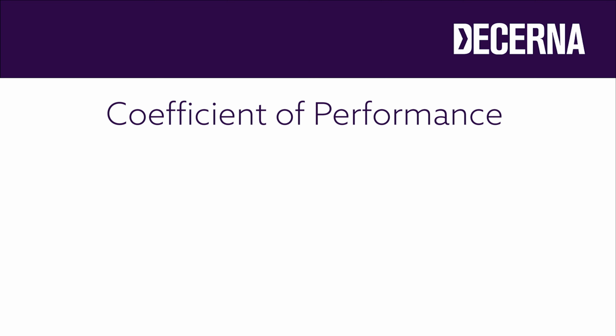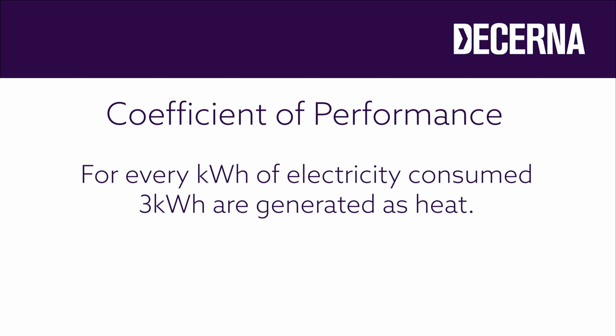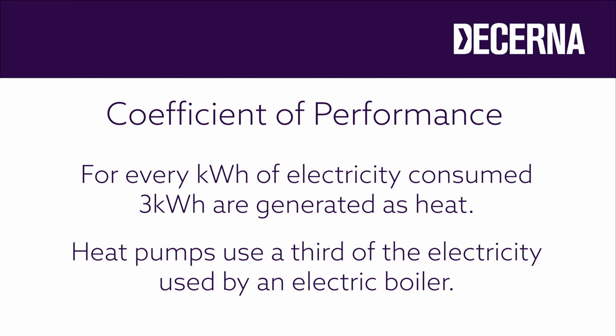And this ratio is called the coefficient of performance, or COP. It's quoted on manufacturers' data sheets to indicate the efficiency of their products. So with a COP of 3, a heat pump will use about a third of the electricity that an electric heating system would use to do the same thing. But what about if you currently heat your building with gas? Well, gas is about a third or a quarter of the price of electricity, but because gas boilers are less than 100% efficient, you can still make a saving with a heat pump.